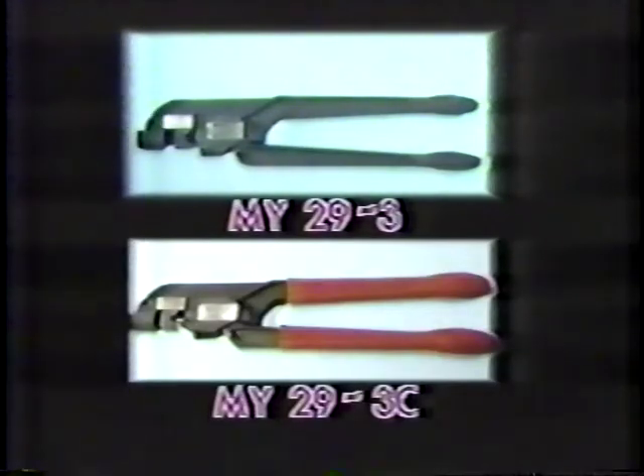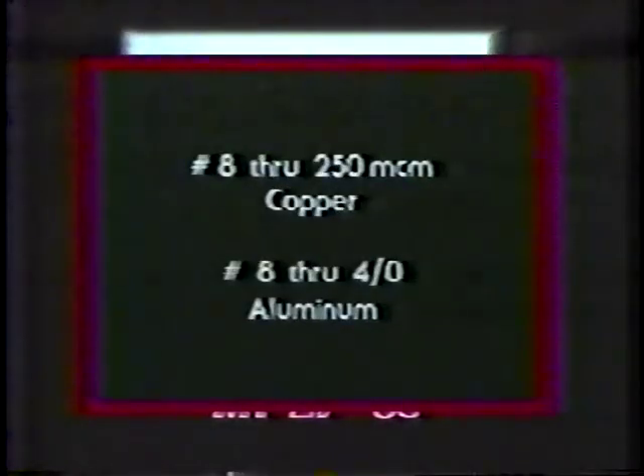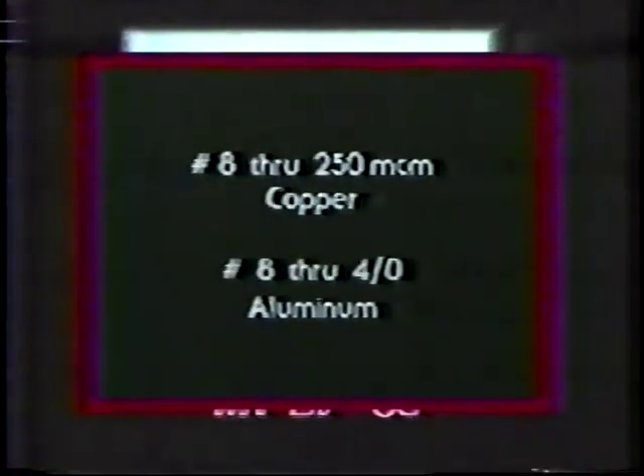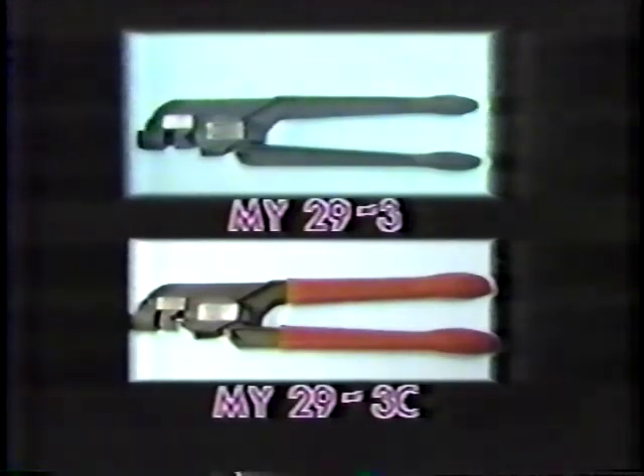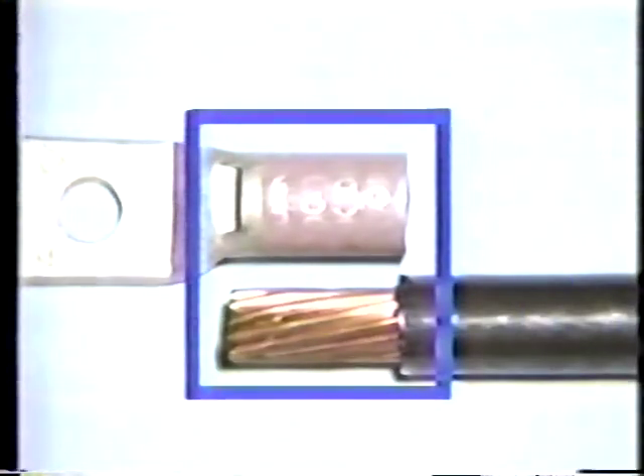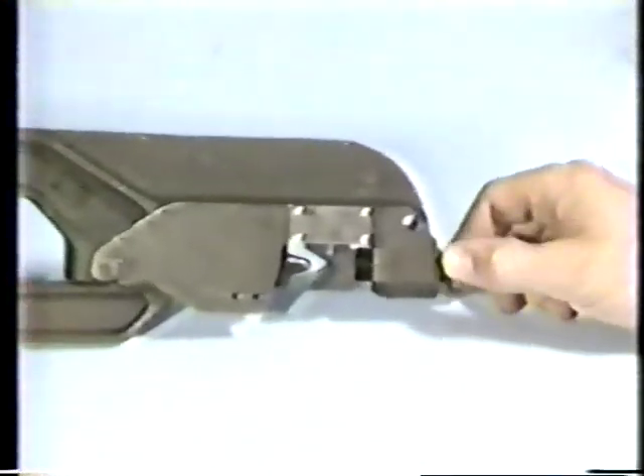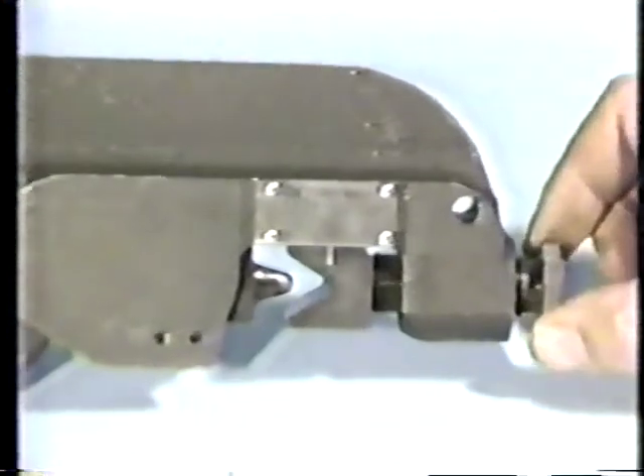The MY29-3 and the insulated MY29-3C are heavy-duty forged dieless tools. They'll install terminals and splices on conductors ranging from number 8 through 250 MCM copper and number 8 through 4/0 aluminum. As you'll see, these tools are extremely easy to use. After using the connector barrel as a guide to strip the cable insulation, adjust the tool's nest die by aligning the white scribe to the wire size being installed.